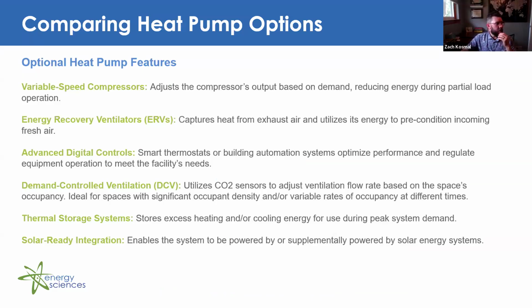So next we have variable speed compressors. These adjust your compressor's output based on demand, reducing energy during those partial load operation. You also have energy recovery ventilators, ERVs, which capture heat from the exhaust air and utilize its energy to precondition incoming fresh air. You also have advanced digital controls. So this would be your smart thermostat or building automation system. These optimize performance and they regulate the equipment operation to meet the facility's needs.